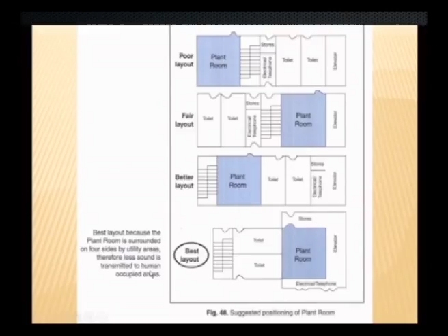The next, fair layout: this plant room is sandwiched between an elevator and a staircase. So, this is slightly acceptable. Then comes the better layout, where the plant room is located between the staircase and a toilet, and the best layout is where it is located by maintenance spaces all around. So, the best layout, because the plant room is surrounded on all four sides by utility areas, therefore, less sound is transmitted to the human occupied areas.